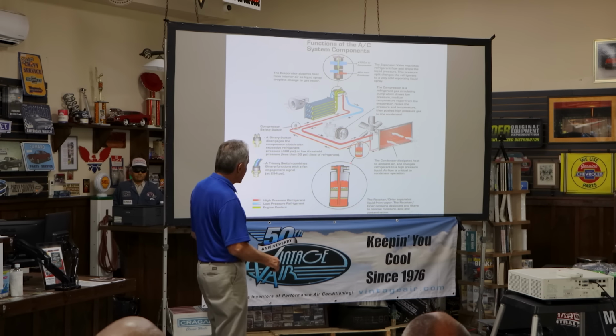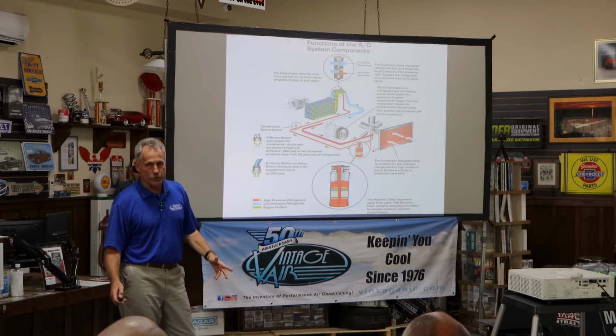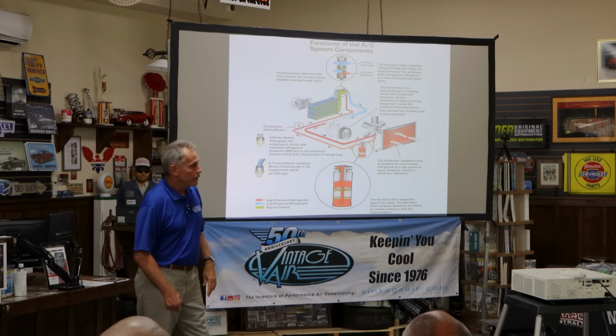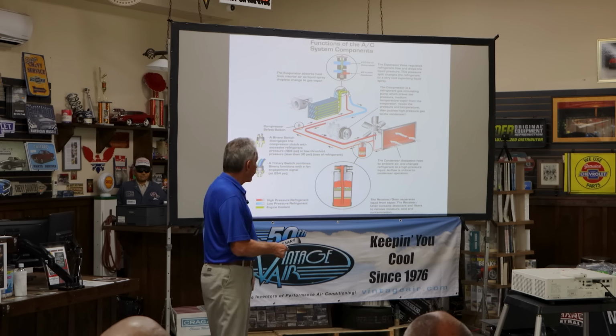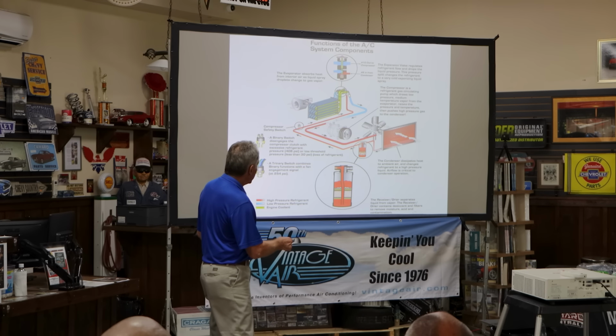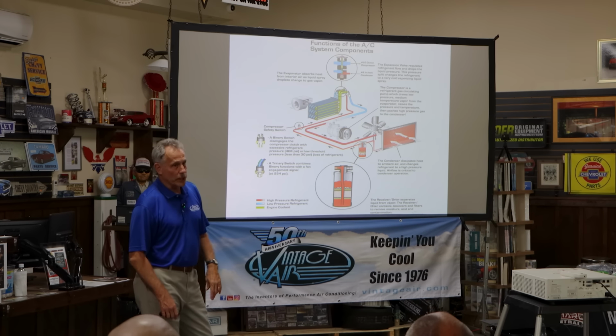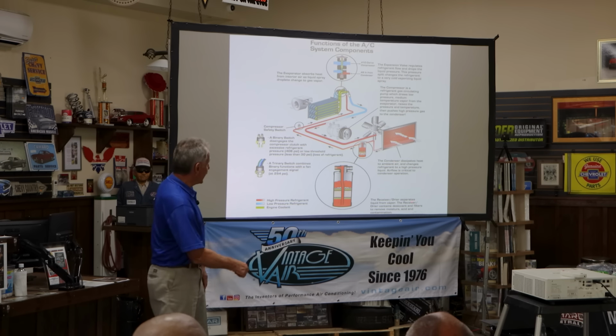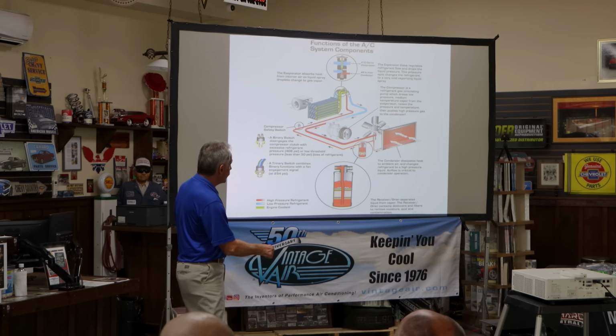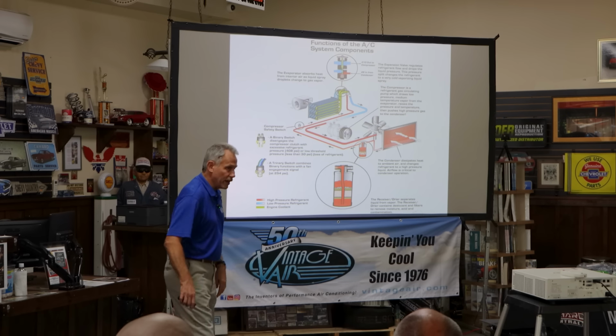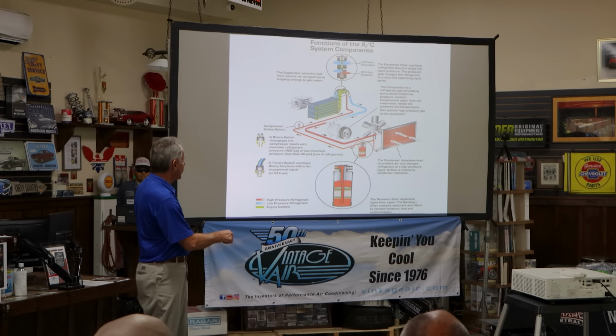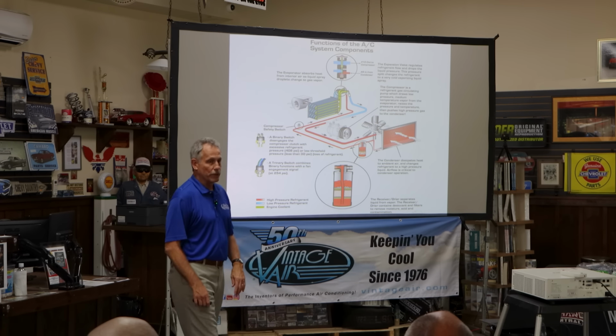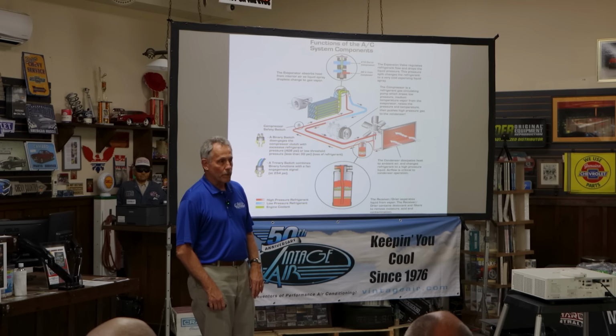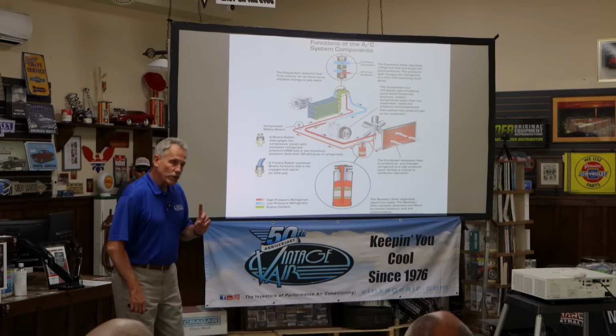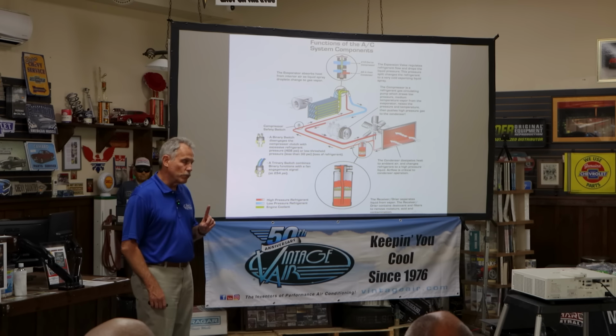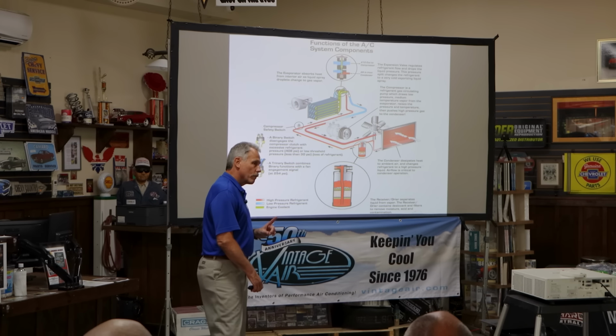Another question we get all the time is, where do I put the receiver dryer in the system? It doesn't matter where in that high pressure liquid line the receiver dryer goes. It can be anywhere from right at the outlet of the condenser to right before the inlet of the evaporator. Anywhere in this high pressure liquid line, you can put the receiver dryer.